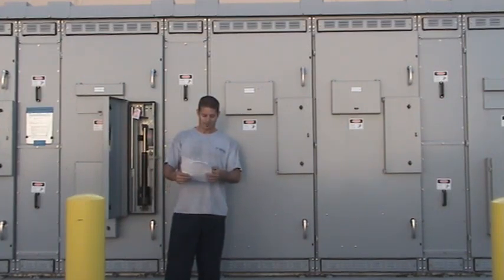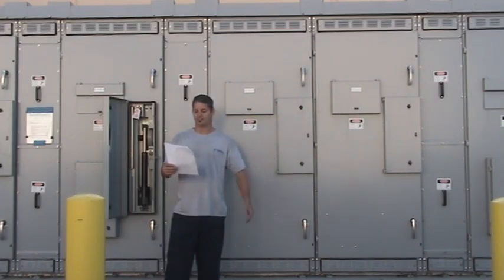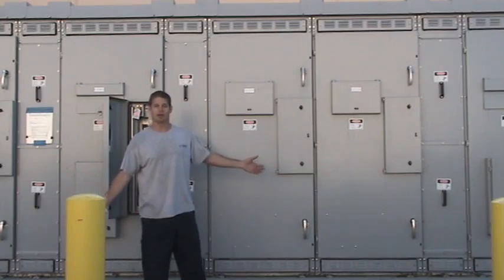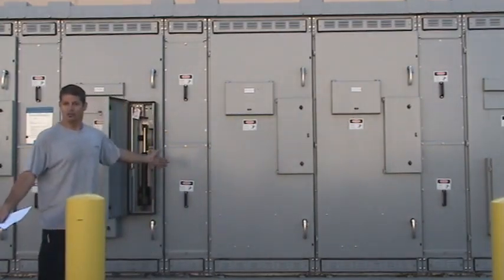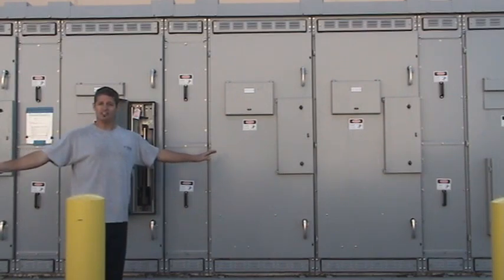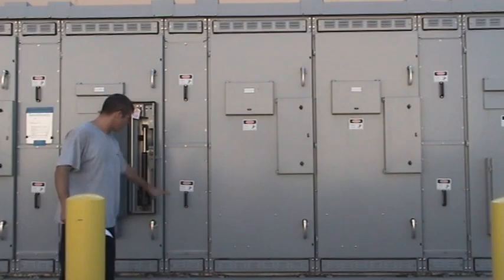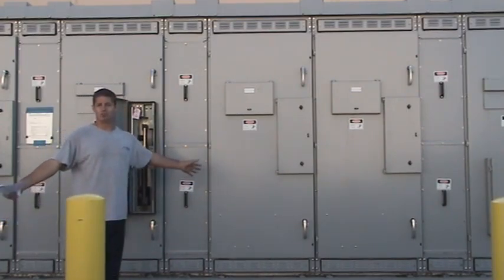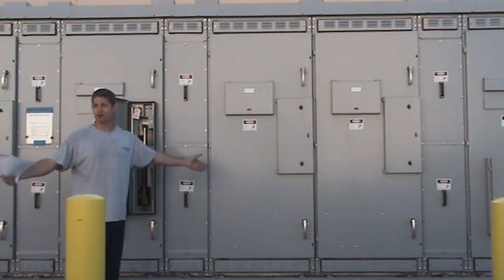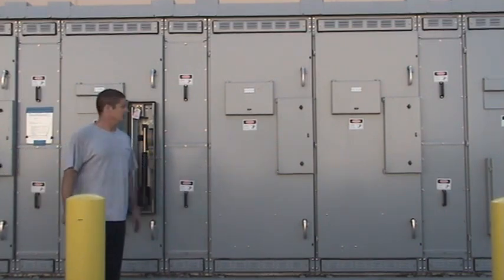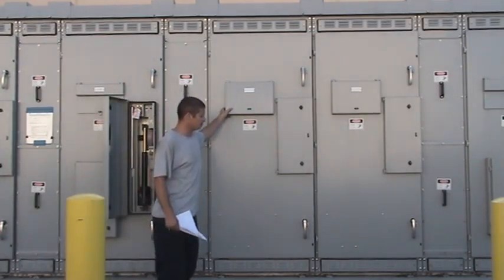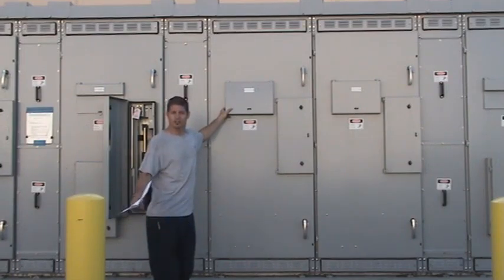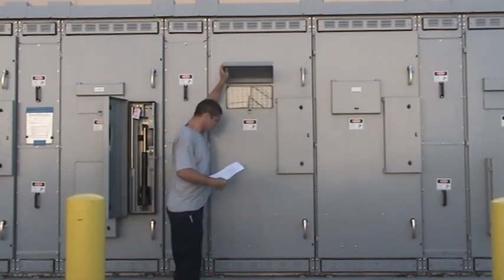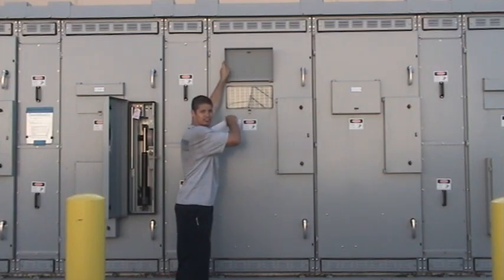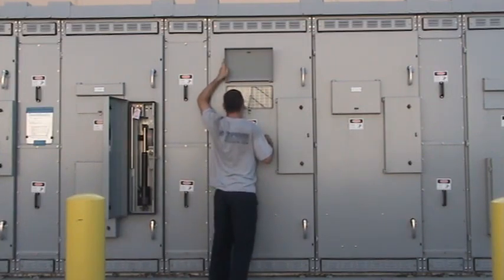The other thing I have on the list is a visual inspection. The thing you want to visually inspect on this gear, obviously, is weather. On the other side you have a sprinkler situation that needs to be addressed, where water's actually puddling under the gear. You don't want water puddling around 12 kV switchgear, so that issue will have to be addressed. The only real visual inspection is to look at the weathering of the switchgear and make sure it's not corrosive or that water's getting into the gear at any point, and visually inspect the blades. Inside here is the only real visual inspection point where you can look into the gear.